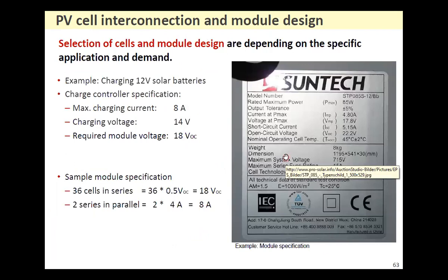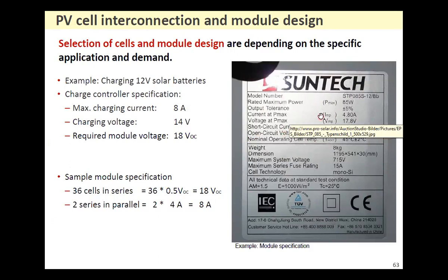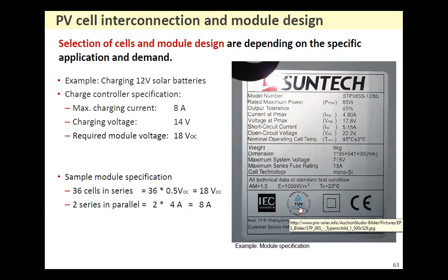Okay. So here comes the example, the nameplate reading of the solar panel. On every module, on the back side, you must see whether certificates are available or not. This is the TUV testing certificate, IEC certificate, and this symbol shows the proper insulation. Ignore this for the moment.